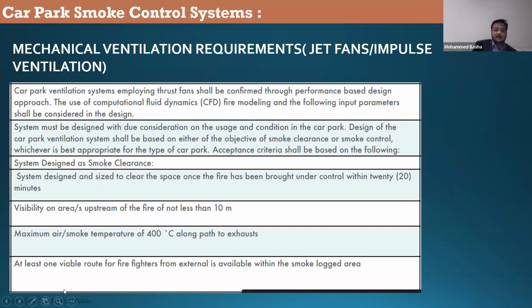If you look at these requirements of civil defense, they say if you are using a smoke clearance system, when you are clearing the smoke, the visibility upstream of the fire should be not less than 10 meters, the maximum smoke temperature 400 degrees Celsius along the path to the exhaust, and at least one viable route for firefighters from the external is available within the smoke logged area.